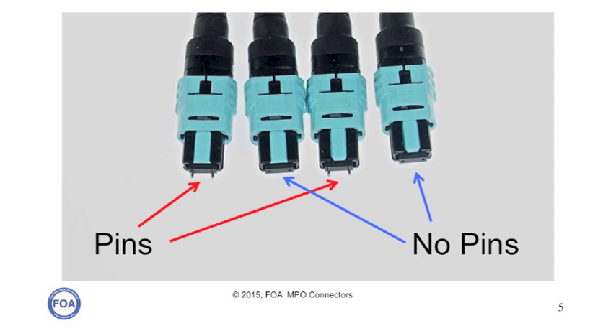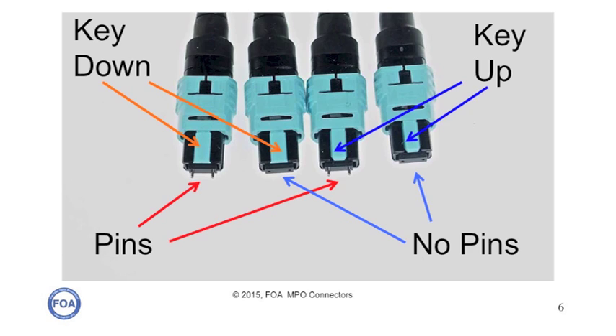The problem you have with most of these connectors is all of the variations in the connectors. As you can see, there are four varieties shown here. First of all, there are connectors that have pins, and there are connectors that have no pins or holes, and those two can be mated to each other to align the fibers using the pins. The second option is the key — the key can be on the top or the bottom, what we call key up or key down, and the keys determine which way the connectors mate. So the pins do the alignment, the keys do the mating.